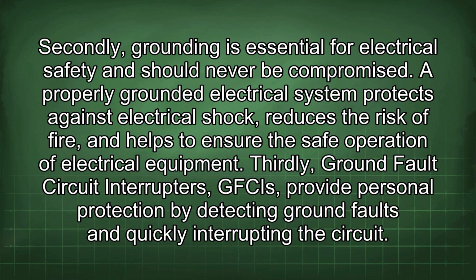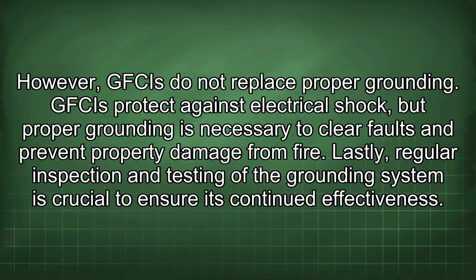Secondly, grounding is essential for electrical safety and should never be compromised. A properly grounded electrical system protects against electrical shock, reduces the risk of fire, and helps to ensure the safe operation of electrical equipment. Thirdly, ground fault circuit interrupters, GFCIs, provide personal protection by detecting ground faults and quickly interrupting the circuit. However, GFCIs do not replace proper grounding. GFCIs protect against electrical shock, but proper grounding is necessary to clear faults and prevent property damage from fire.